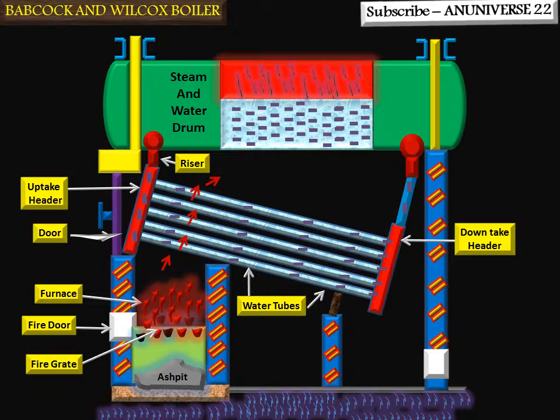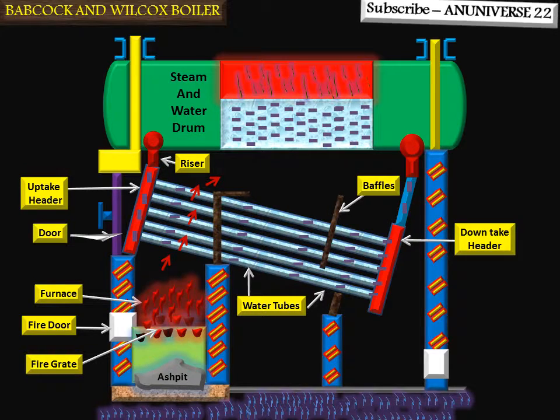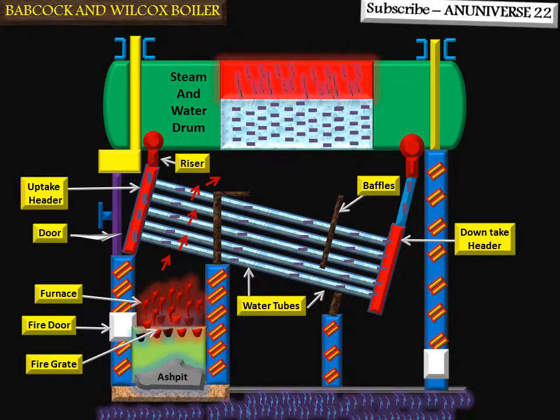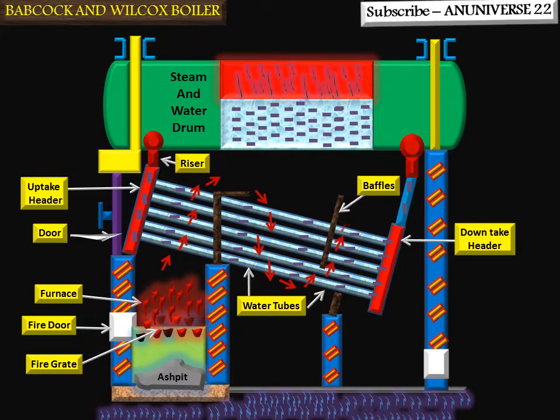Baffles are arranged across the water tubes to provide gas passes, and these also act as deflectors. Baffles divert the flue gases so they flow more than one time through the tubes, and more heat is transferred. Here, two baffles are arranged which provide three passes of flue gases.